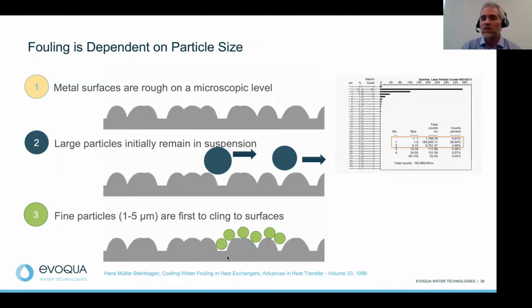And what it shows you is the water quality can be broken down into various different buckets: less than 1 to 5 micron, 5 to 15 micron, all the way up to 100 micron. And when we've taken various different samples throughout many of our sites and our customers, we see that the majority of particles by count, over 95% of the particles, are actually less than around 15 microns. So again, it is very important to understand what's in your water so you can select the right technology.